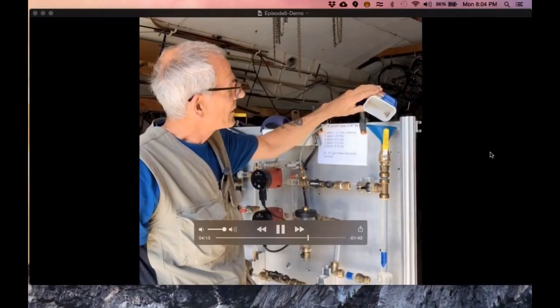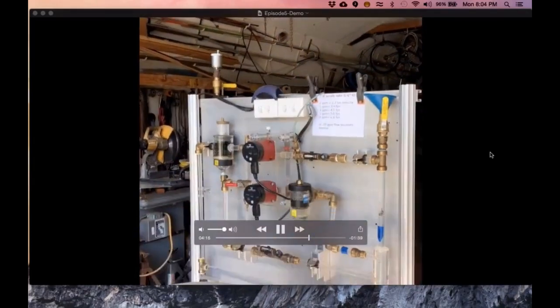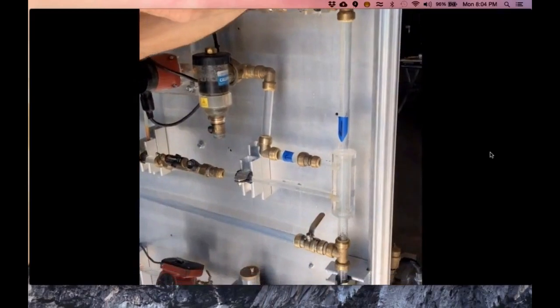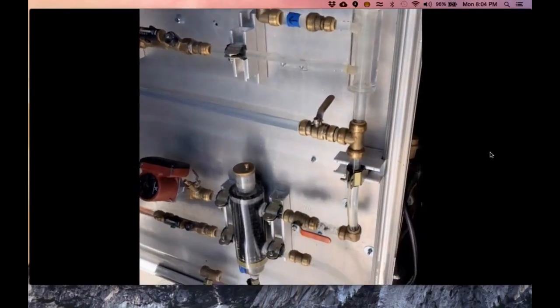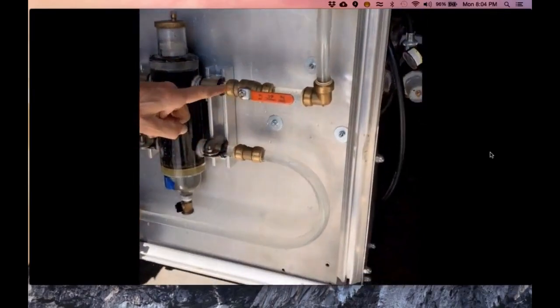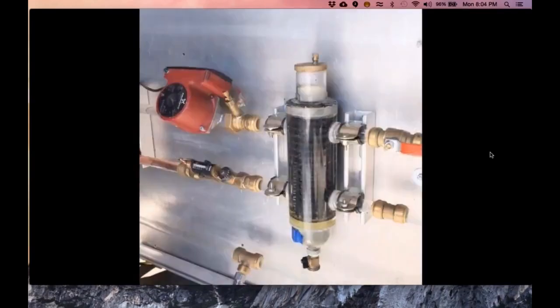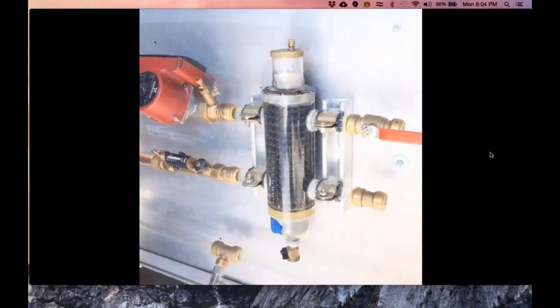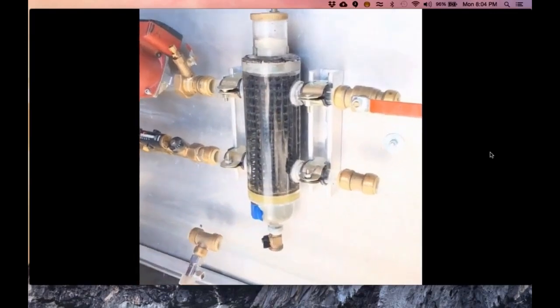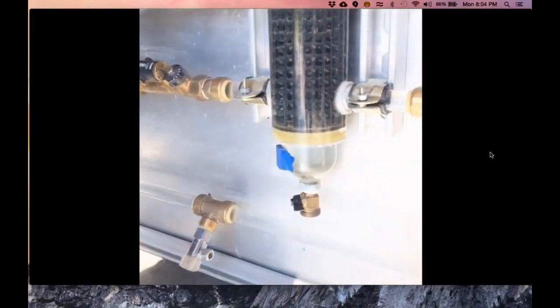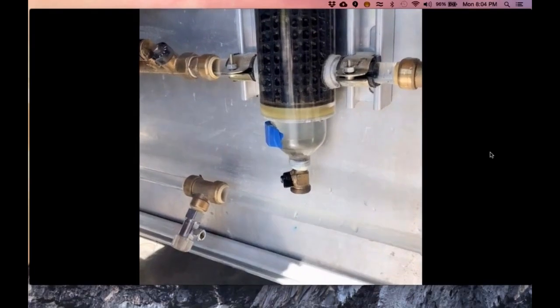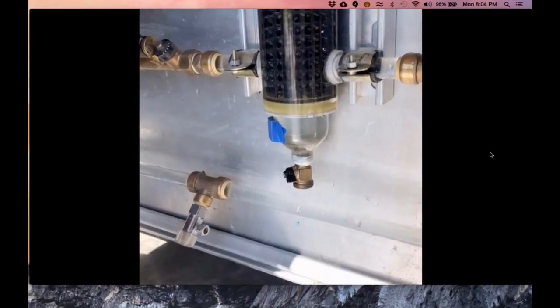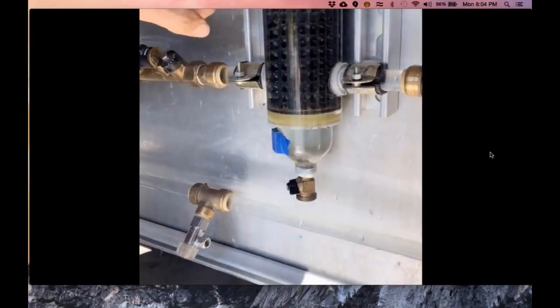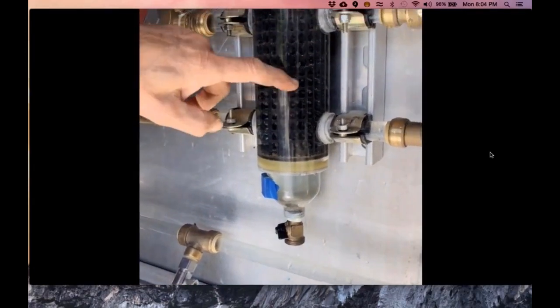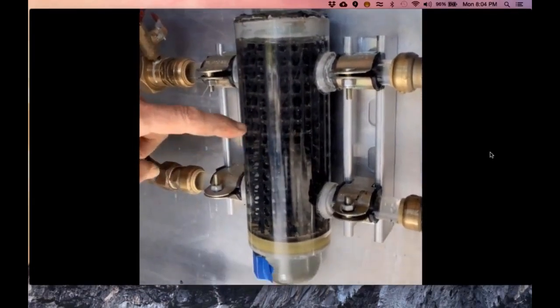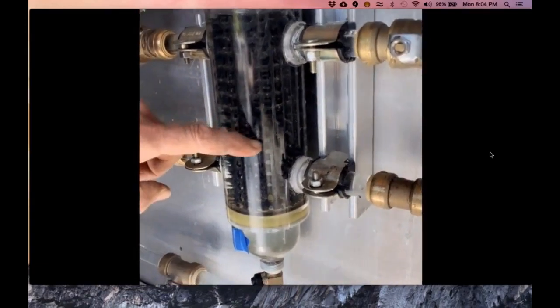All right, let's put a little bit of particle in there, or put clear water in so you can see this a little bit better. And then we'll go down below and we'll run this for a minute. And let's see, down through the air coming out because I just refilled it. You can see I got my magnet taped on the bottom here. So we're going to give that just a second to run since I just put it in there. Speed it up a little bit. I don't know if you can see the little particles starting to come down here. See them filtering down. I've got some copper in there. I've got some stainless particles. I got some aluminum in there.